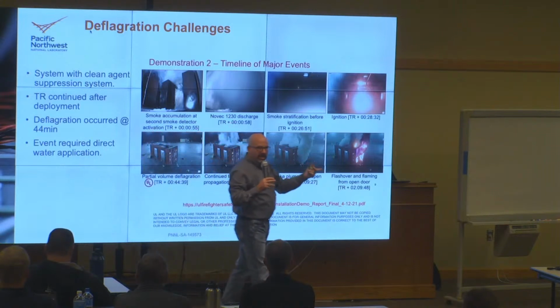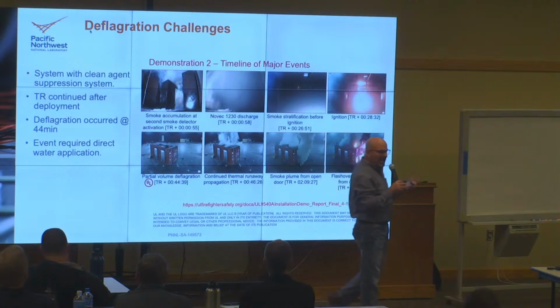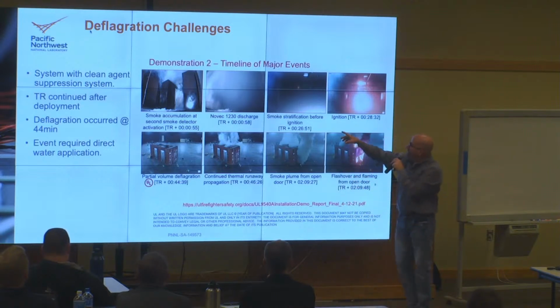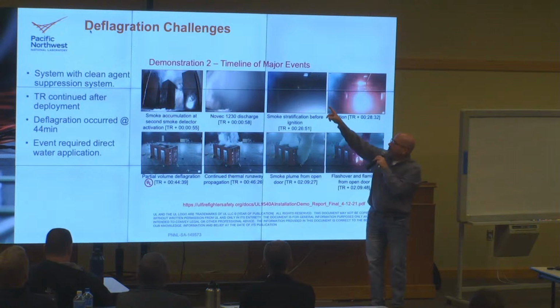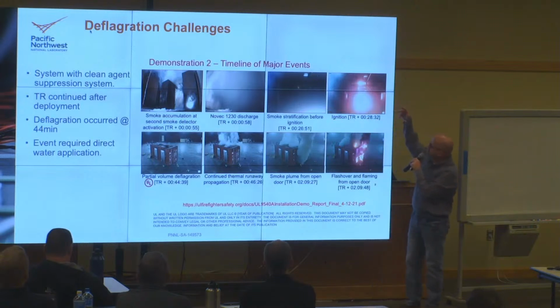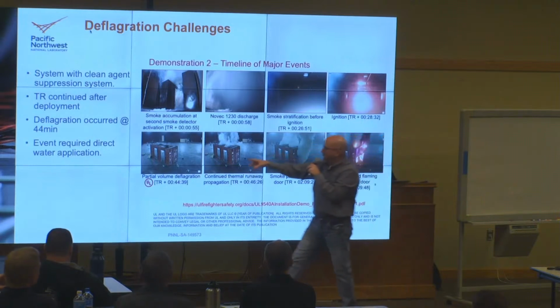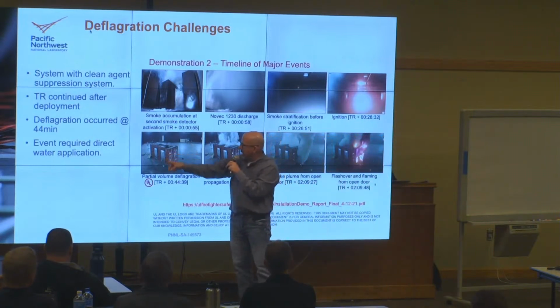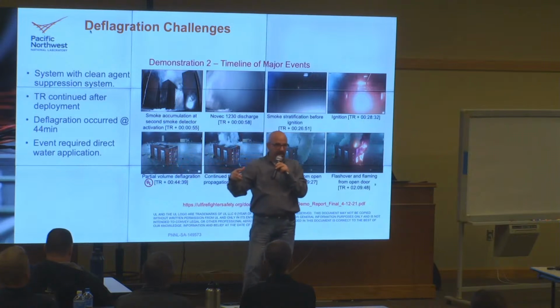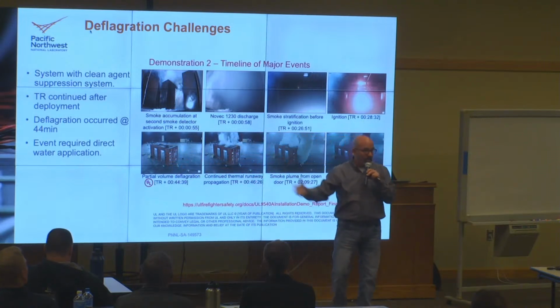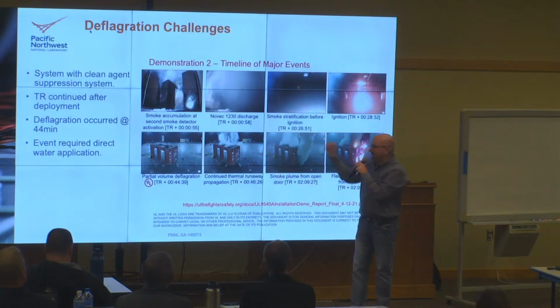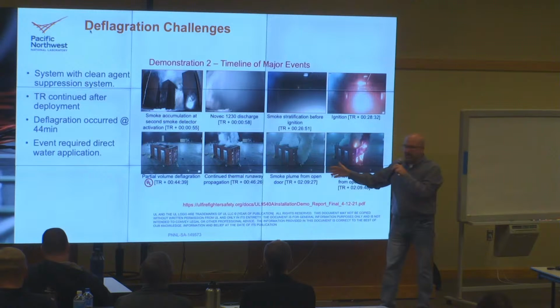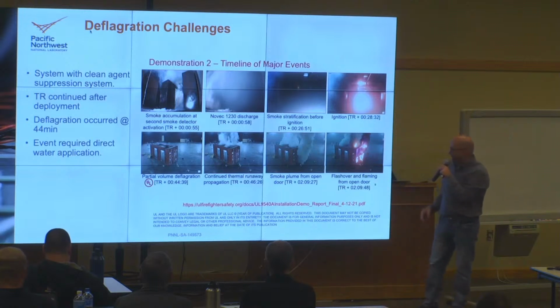Well, clean agent has a limited soak time, all right? About 10 minutes, typically, is the design point. So at about 26 minutes, it's stratified and thermal runaway continues. It ignites at 28 minutes, and they have a partial volume deflagration in this test chamber at 44 minutes. And these are half PSI vents on all sides, all right? So they have a lot of square footage on there. You would not have that on a typical cabinet. Thermal runaway continues. At 2 hours and 9 minutes, they stop the test and open the door, flash over, and they have to direct a hose line in there to terminate it, all right? So that's with a clean agent.